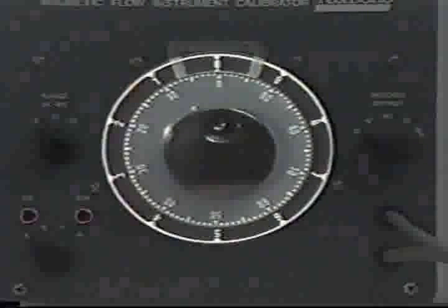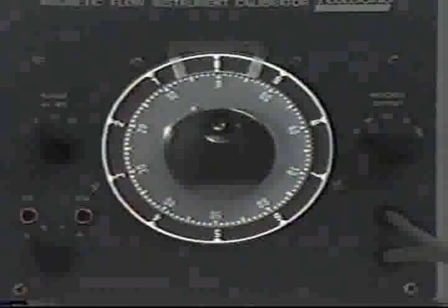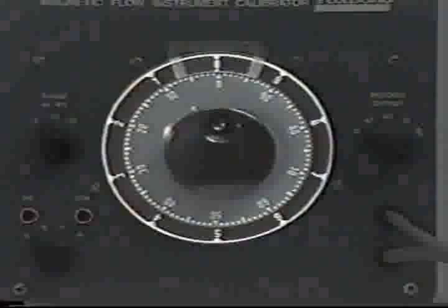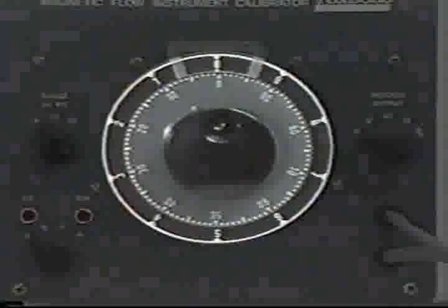The input power indicators, when lit, show the value of calibrator input power. This calibrator will operate with either 118 or 236 volts AC nominal power. This switch is used to set the correct line voltage, as indicated by the lighted input power indicator. The switch can be set in two positions for correct phasing, either F for forward or R for reverse. The turns counting dial divides the maximum output set on the AC millivolt range switch in 1,000 equal increments. Each minor division of the dial has a value of 5, 10, or 30 millivolts.